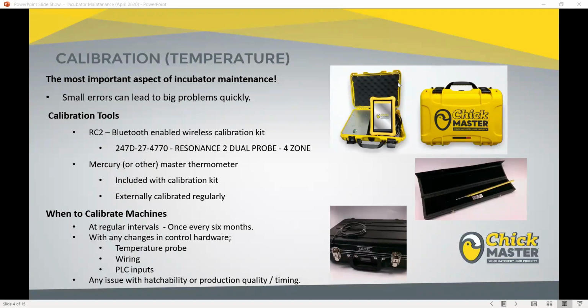So that's your temperature probes, your PT100s. On a Gen 4, Gen 3, and an ultra control, you're going to have one of those per zone. And on a rock control, you're going to have two of those probes per zone. If any of those get changed because of mechanical damage or perceived weakness in those readings, you need to recalibrate once that's been done. The reason being, your calibration value is based on the resistance within that electrical circuit. And as soon as you change any hardware, that resistance changes and your calibration offset will change appropriately.